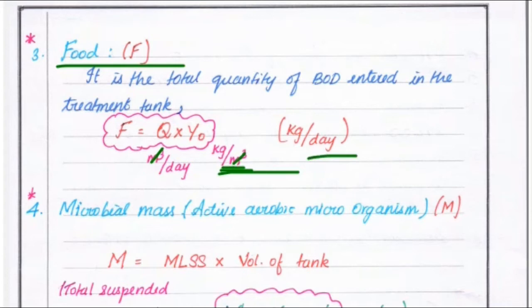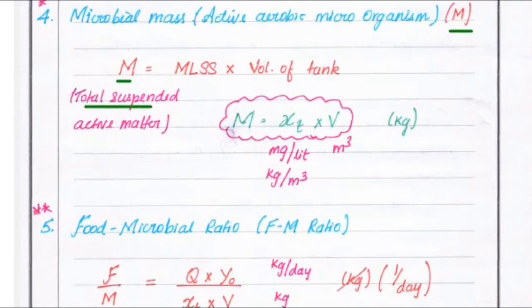Next is microbial mass, that is activated aerobic microorganisms, M. The formula is M equal to MLSS into volume of tank — total suspended active matter equals MLSS into volume of tank. So M equals XT into V, where XT is in kg per meter cube and V is in meter cube, giving a unit of kg.